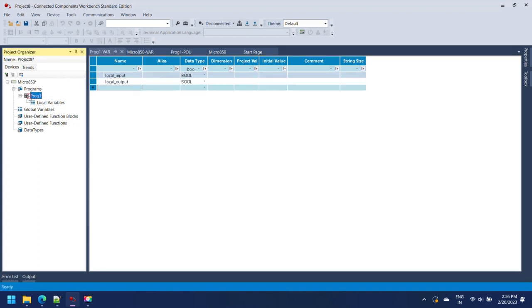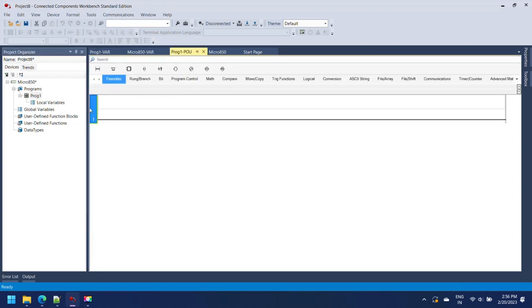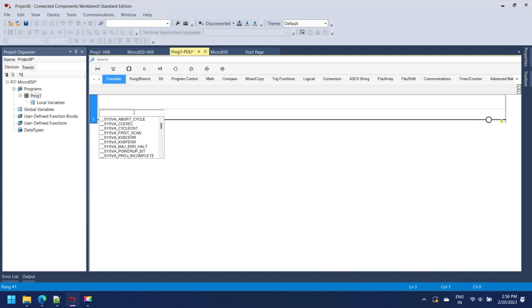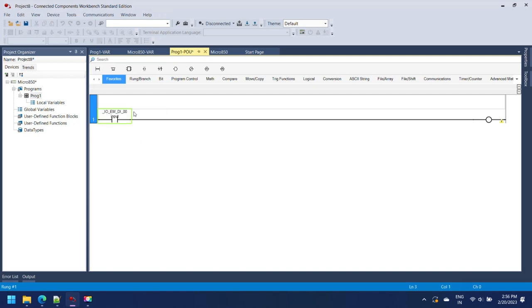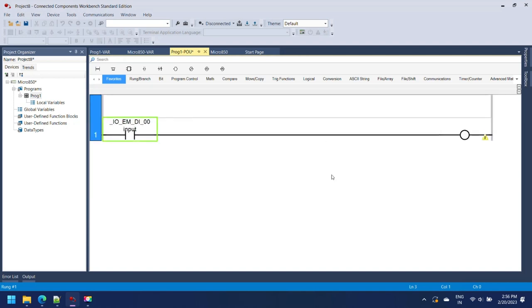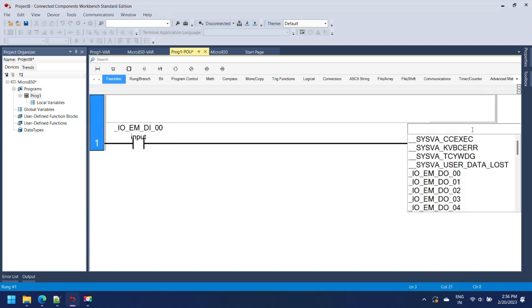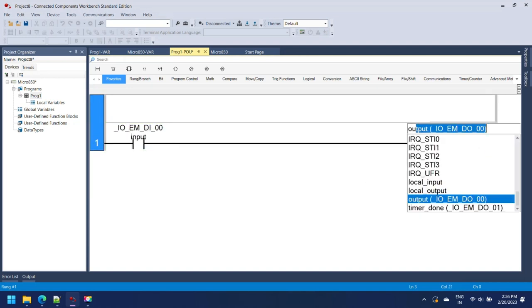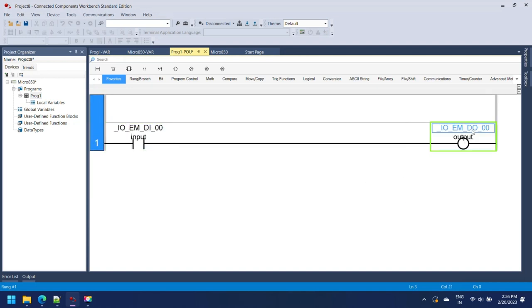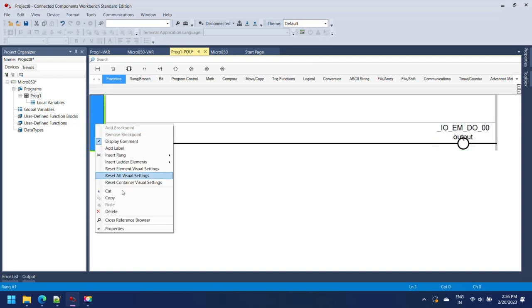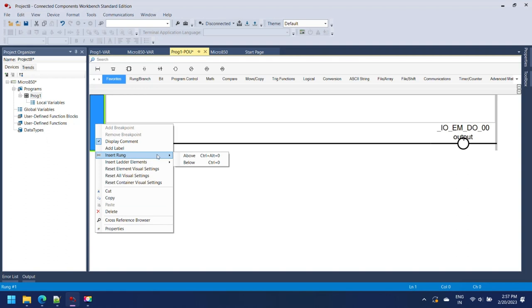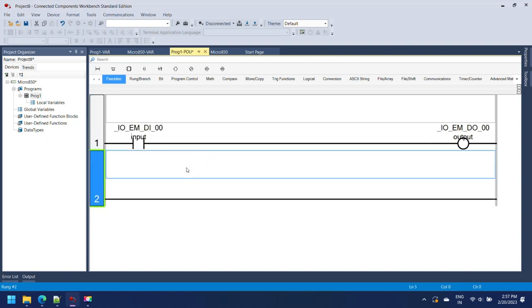Now open your program and add some logic and define the variables for input and output. Here I am making three rungs. First, simple input and output declaring global variable. Second rung, input and output declaring local variable for instruction. Third rung, I am adding a timer on the rung and declaring preset time for the timer.